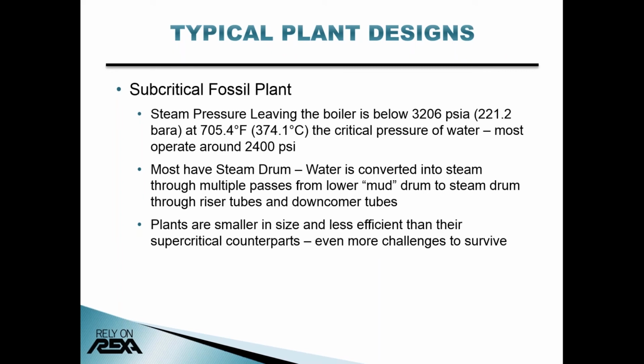First, a subcritical plant or boiler operates below the critical pressure of water at 3206 psia and 705 degrees Fahrenheit. The subcritical boiler design goes back to the early 1900s and includes a steam drum where the steam loop begins and ends. With a natural circulation through the tubes due to a density change from water to steam, water is boiled only partially, protecting the tubes. Steam is then drawn off the steam drum, sent to superheaters, and onto the turbine. These are smaller plants and usually operate in the 32 to 35% efficiency range.